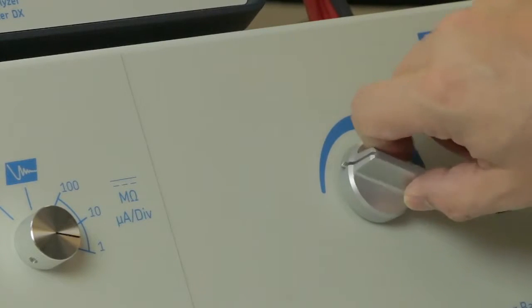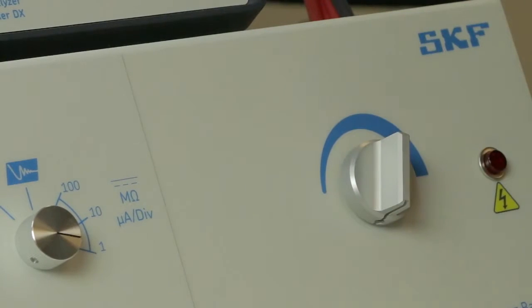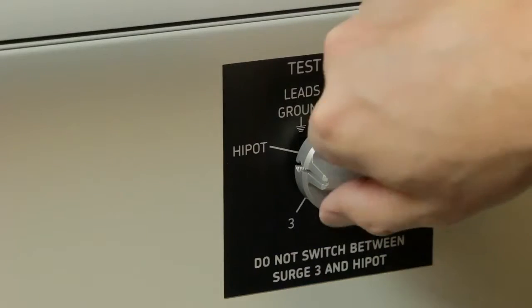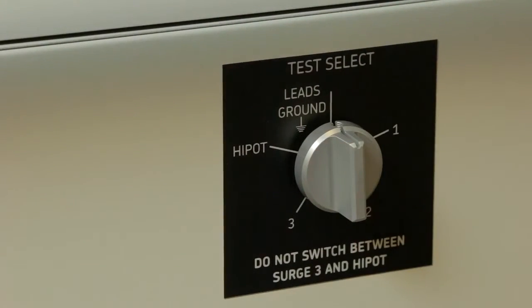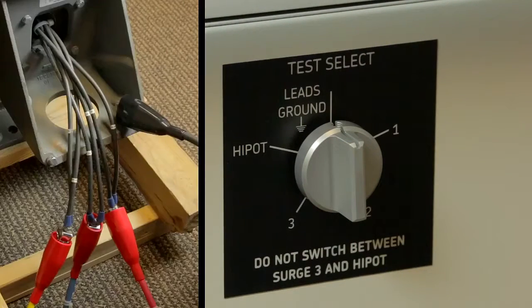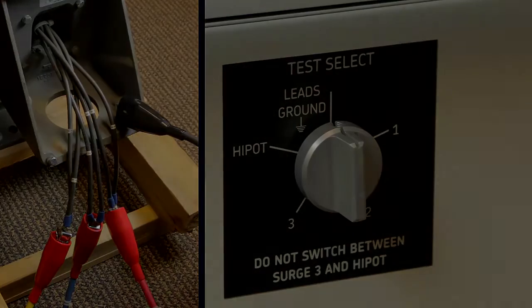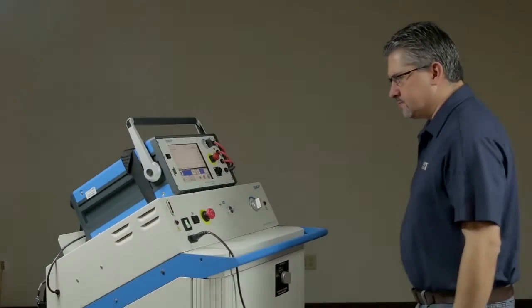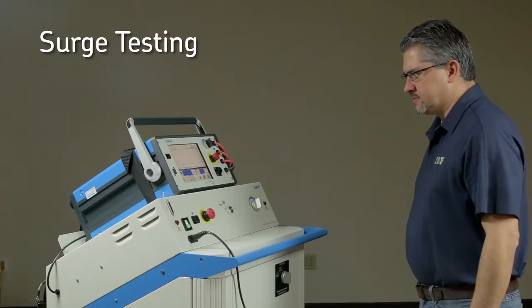Return the voltage knob back to 0. Turn the test select knob to the leads ground position. The DX will remind you to do this. To ensure the test circuit is adequately discharged, maintain the ground connection after testing for the same duration as the high voltage was applied. Now we'll perform surge testing on this 3-phase motor.